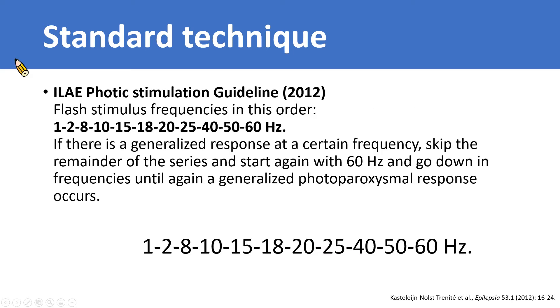Another good method for performing IPS was proposed by ILAE in 2012. As shown here, the flash stimulus frequencies are delivered in a specific order. If there is a generalized response at a certain frequency, skip the remainder of the series and start again with 60 Hz, going down in frequencies until again a generalized photoparoxysmal response occurs.